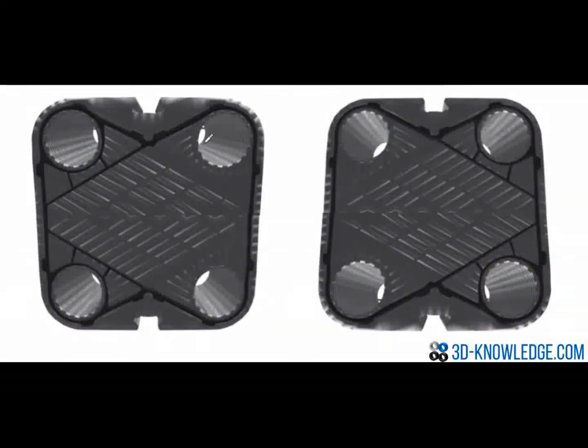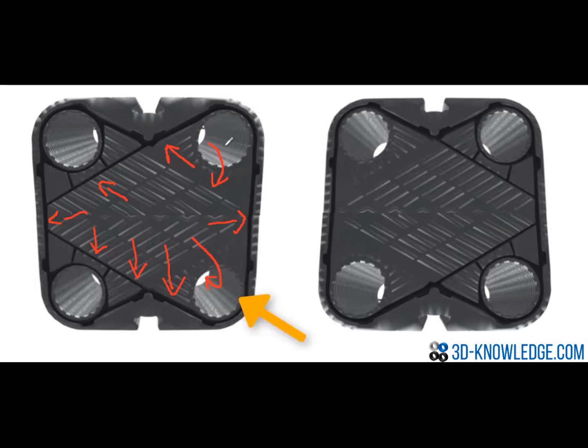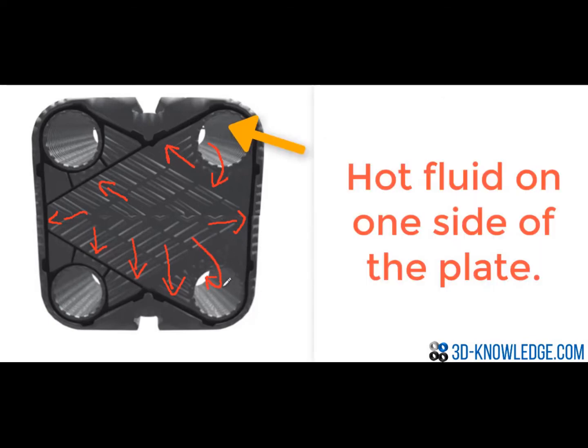Let's imagine for a moment that the plate has a fluid flowing through it, and this fluid is hot. So it would be coming through here, and it would enter the plate space. Now each of these plates are pushed up tight against each other, so the fluid will only ever be able to flow up to the boundaries of the gasket. And the boundaries we can see here. And then once it's occupied the whole space within the gasket area, it will exit through this hole here. So we have an inlet on the top for the hot fluid and a discharge on the bottom.